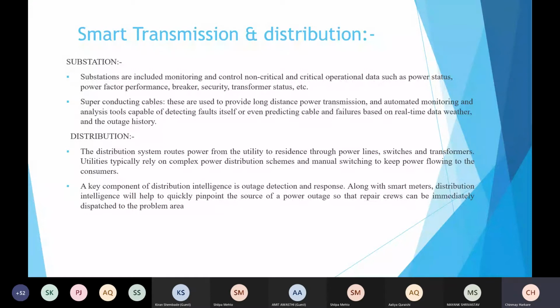The data cables normally proposed are fiber optic cables, and the advantage of fiber optic cable is it can be laid with high voltage cables also. So the electromagnetic interference that we talk about in electrical and electronics engineering doesn't come into picture. Otherwise, if data cables are wired copper cables, you have to take a lot of precautions to keep safe distance between two cables, and unnecessarily the duct size increases in cross section. So everywhere we have proposed fiber optic cable be laid, so that for audio, video and smart metering purposes, complete data can be transmitted through the optical fiber cable.